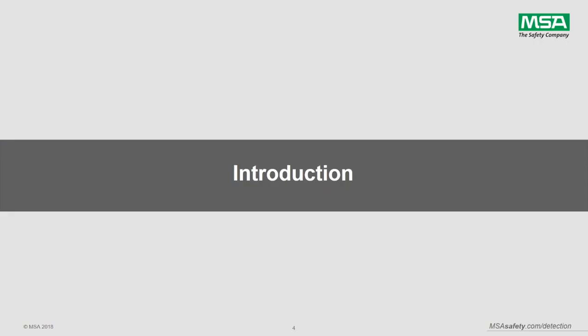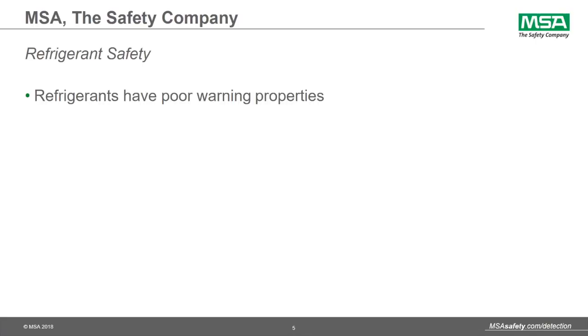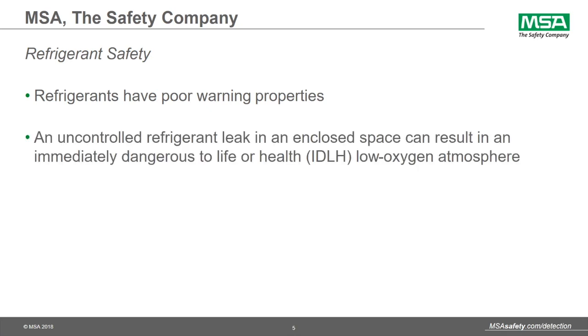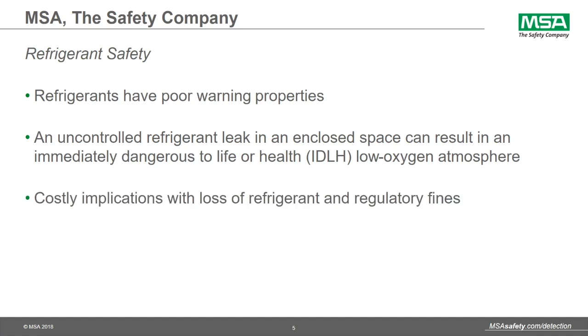The topic today is really around refrigerant safety and its importance. There are 3 reasons why we detect for refrigerants: for safety, for environmental, and for economic reasons. For refrigerant safety, refrigerants have poor warning properties. An uncontrolled refrigerant leak in an enclosed space can result in an IDLH, or immediately dangerous to life or health, environment. There's also costly implications with loss of refrigerant and heavy regulatory fines.